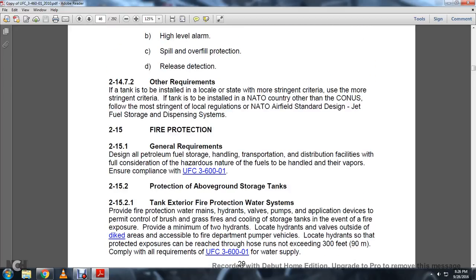215 Fire Protection. 215.1 General requirements: design all petroleum fuel storage, handling, transportation, distribution facilities with consideration of the hazardous nature of the fuel to be handled and its vapors, ensuring the compliance with the UFC 3-600. 215.2 Protection of above ground storage tanks.